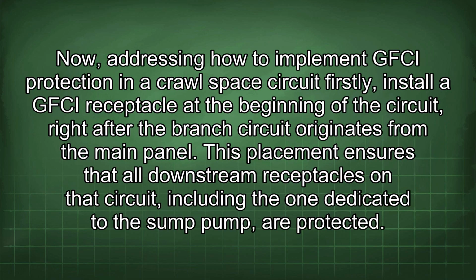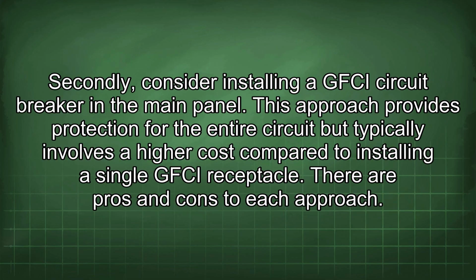Now, addressing how to implement GFCI protection in a crawl space circuit. Firstly, install a GFCI receptacle at the beginning of the circuit, right after the branch circuit originates from the main panel. This placement ensures that all downstream receptacles on the circuit, including the one dedicated to the sump pump, are protected. Secondly, consider installing a GFCI circuit breaker in the main panel. This approach provides protection for the entire circuit, but typically involves a higher cost compared to installing a single GFCI receptacle. There are pros and cons to each approach.